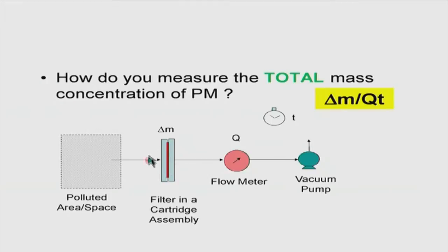One more time, delta M, okay? There are many instruments available that are at a 10 microgram level resolution. But sometimes for the work we do, we require something which has a resolution of 1 microgram.